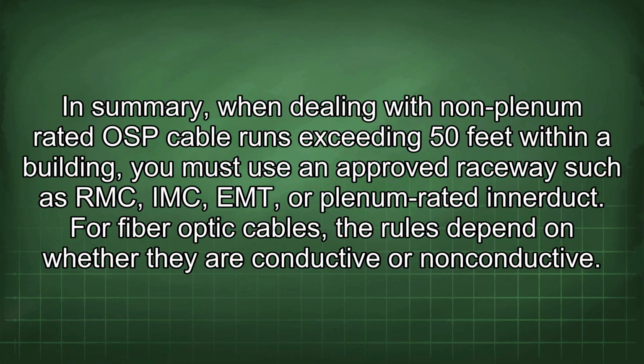system. In summary, when dealing with non-plenum rated OSP cable runs exceeding 50 feet within a building, you must use an approved raceway such as RMC, IMC, EMT, or plenum rated innerduct.